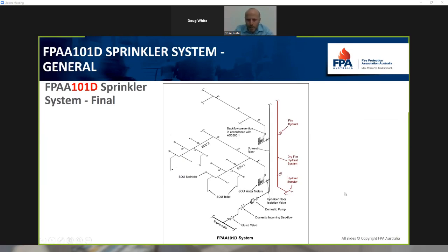So the schematic really is showing us that this is showing 2 floors, for example, and we'll look closely at the details, but you'll see also that there's an independent dry fire hydrant, which is that concession that we spoke about, and it's not connected to a water supply. And by the way, that's a concession, but it's not a requirement. So if somebody wants to use a wet hydrant system to protect a 101D system, go ahead. There's no issue there. This is just a concession that allows a dry hydrant.